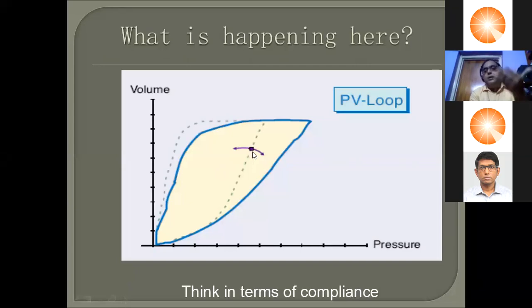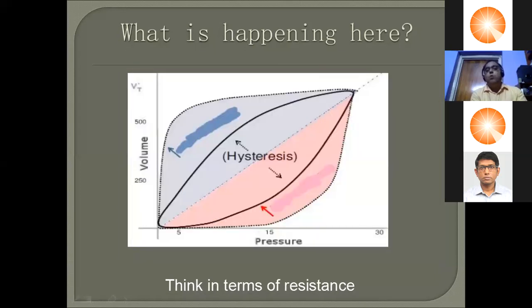And how do we use it? Suppose I have got a lung. The PV loop was looking like this dotted line before, and now it is looking like this. It looks as if it is trying to lie down and go towards the x-axis. If that happens, what does it mean? Consider this point. Previously at this point, my pressure was somewhere over there and my volume was somewhere over there. But now on this new loop, my pressure remains the same, but for the same pressure, my volume is much lower. So for the same pressure, I am having much less volume. What is happening? My compliance is going down. As your compliance is going down, the PV loop will go towards the x-axis. So that tells you that the lung is getting worse.